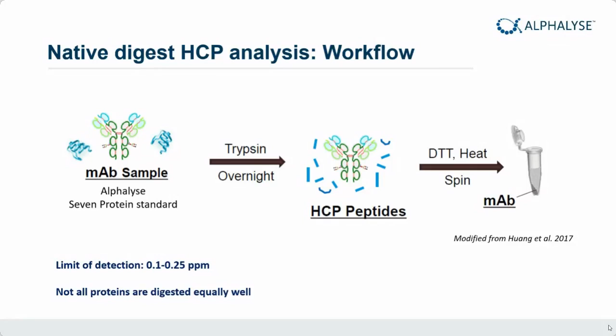We have adapted it to our laboratory, and also we add our 7-protein standard. Again, for QC purposes. And what we see is that 6 out of 7 of these protein standards have a limit of detection around 0.1 to 0.25 ppm, which is around 10-fold lower than our standard HCP analysis. But what we can also see is that we have one standard that does not digest as well. So we prefer not to use it for quantification. We mainly use it for identification, and then knowing that the HCPs are present at a very low level.